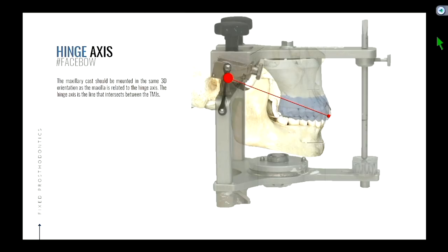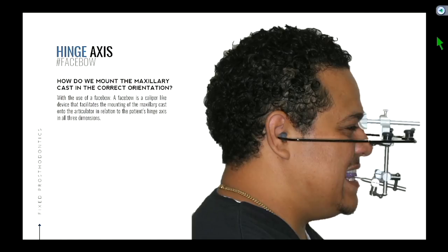You can see how this instrument starts to mimic what our jaw does. The maxillary cast should be mounted in the same three-dimensional orientation as the maxilla is related to the hinge axis — the line through the heads of the condyles, or on your articulator, the line through the two big balls. To mount the maxillary cast in the correct orientation, we use a device called a face bow — a caliper-like device that helps us get the correct distance and orientation in all three dimensions.